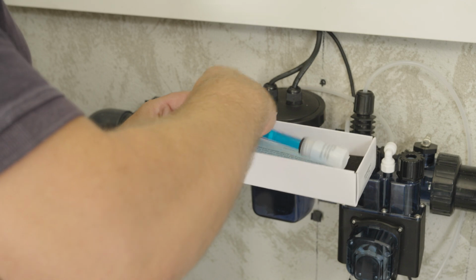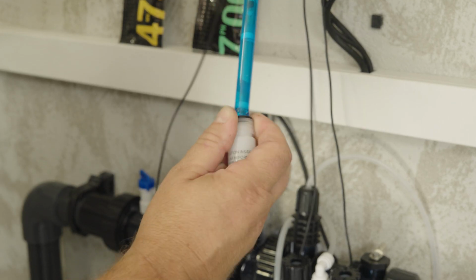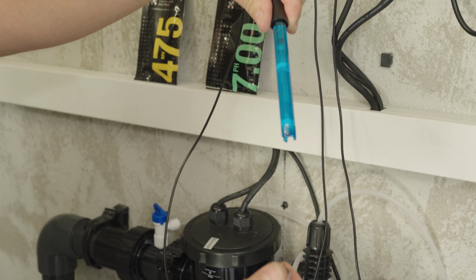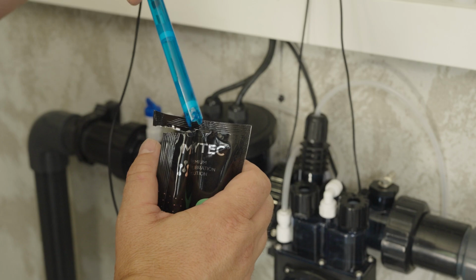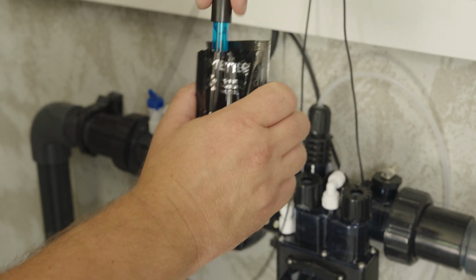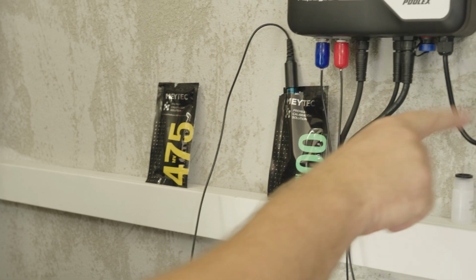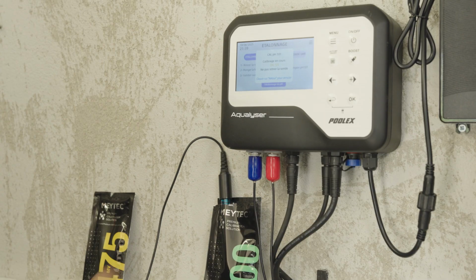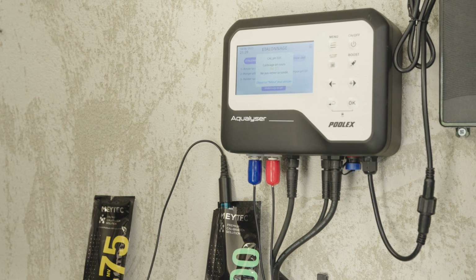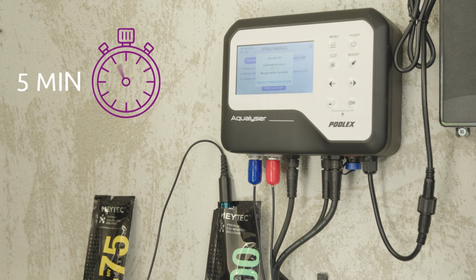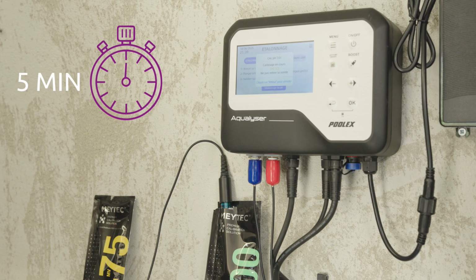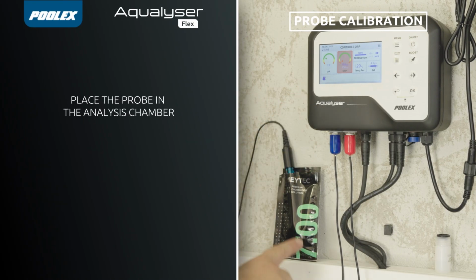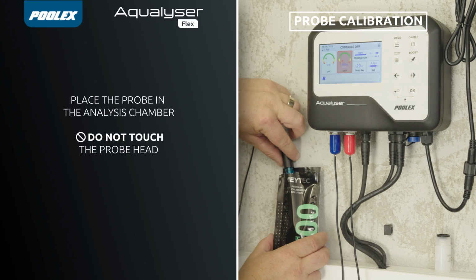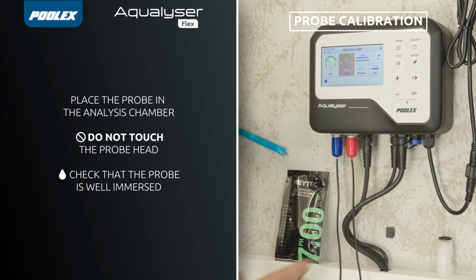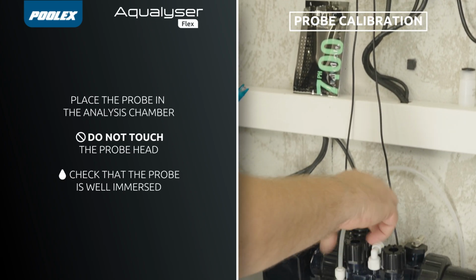Remove the probe from its holder and immerse it in the pH 7 buffer solution. Press OK. Calibration begins. Leave the probe in the solution for 5 minutes. You can now place the probe into the probe holder of the analysis chamber. Warning: do not touch the probe head with your fingers and check that it is well immersed in water.